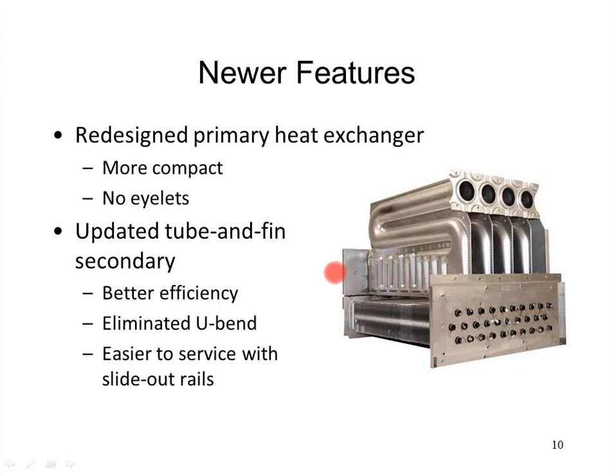And they wrap around the back side over here. And then all the gas comes through these individual tubes. There's 3 rows of them here, as you can see, multiple columns. We're going through all these stainless steel tubes, and there are fins on those tubes to help spread the heat out. And then you probably can't see it very well in this picture on the webinar, but you might see little tabs sticking out of each one of these guys. Each one of those little tabs sticking out of each one of them is a little turbulator.